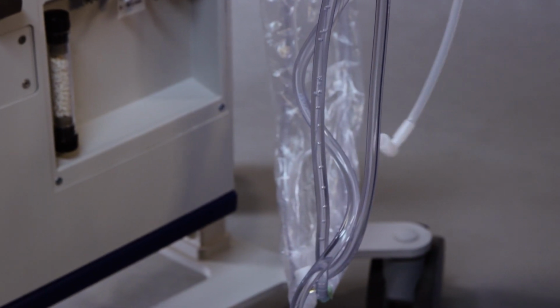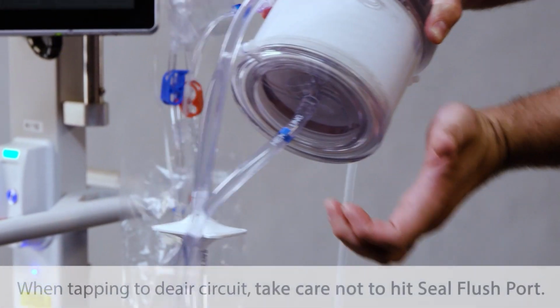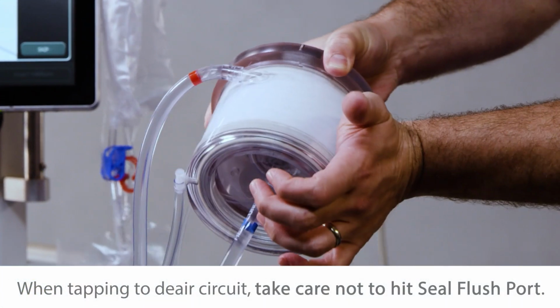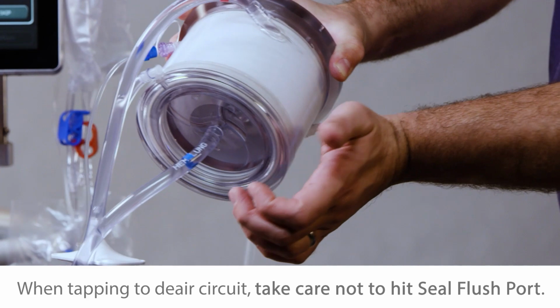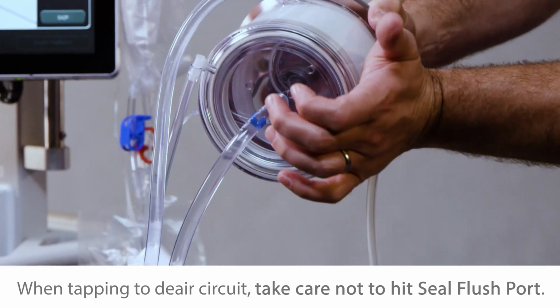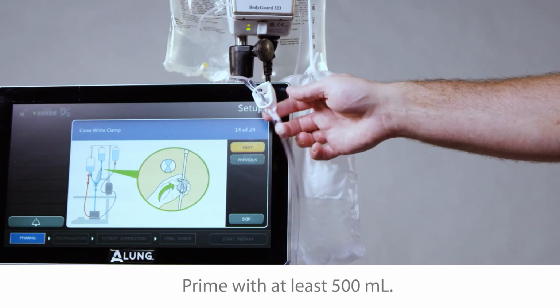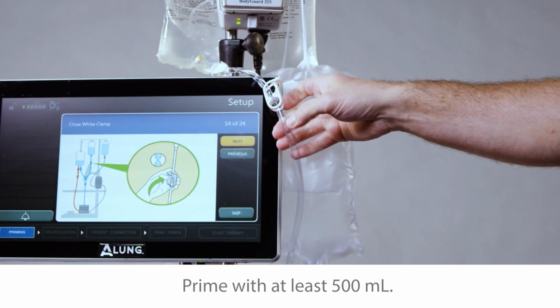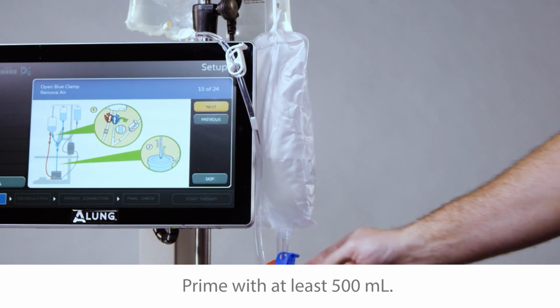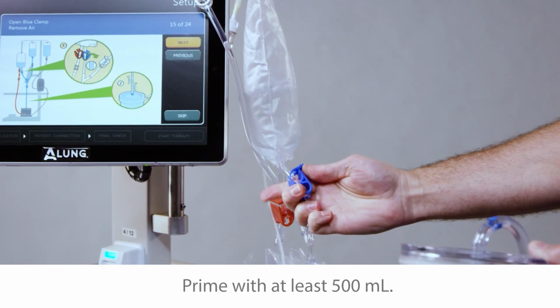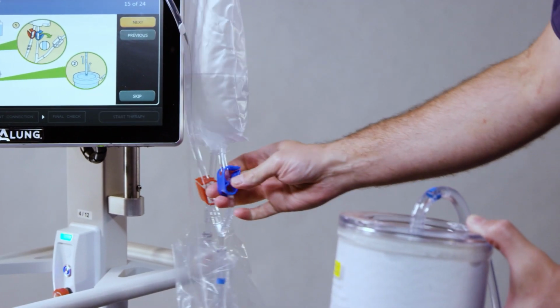Fill the cartridge by keeping the red port up and the entire cartridge below the saline bags. Tap the side to remove any trapped air. Once the circuit is filled with a minimum of 500 milliliters, close the white clamp. Now open the blue clamp to allow any trapped air to enter the recirculation bag.